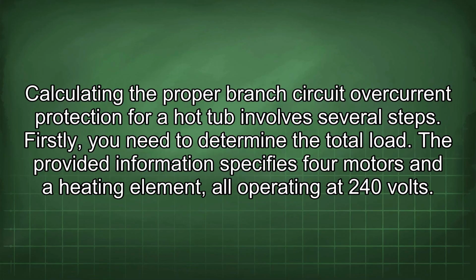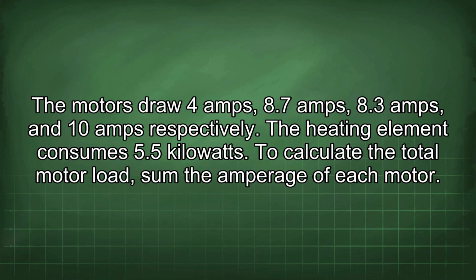Calculating the proper branch circuit overcurrent protection for a hot tub involves several steps. Firstly, you need to determine the total load. The provided information specifies 4 motors and a heating element, all operating at 240 volts. The motors draw 4 amps, 8.7 amps, 8.3 amps, and 10 amps respectively. The heating element consumes 5.5 kilowatts.